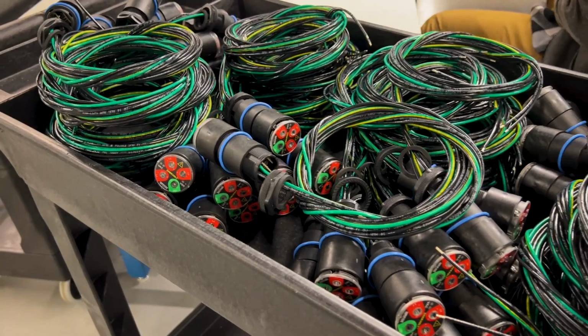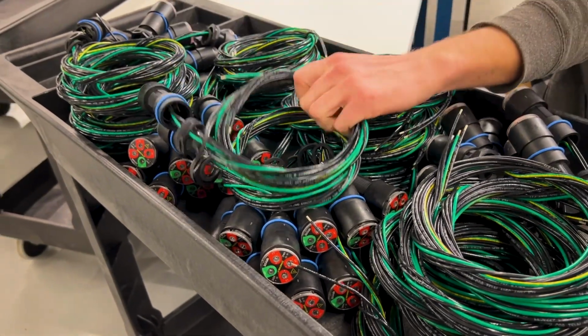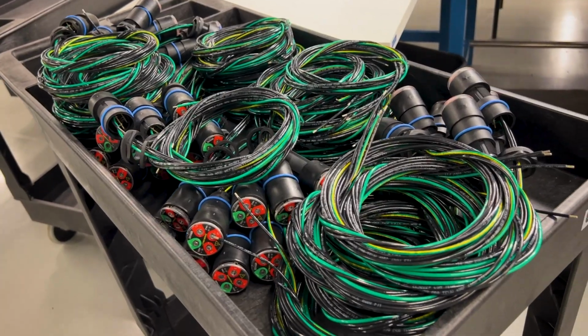On the back side of the product, when it's installed, what's going to be inside the cabinet? Can you tell us about the wire gauge and the length of the wire? Sure. The standard check volt comes with an 8-foot wire, 14 gauge, UL style 1452, which is PVC extruded with nylon over the PVC extrusion to help with gasoline and chemical resistance. That's a good wire to use in industrial cabinets. It's rated to 1,000 volts at 90 degrees C, and it's typical for this application.